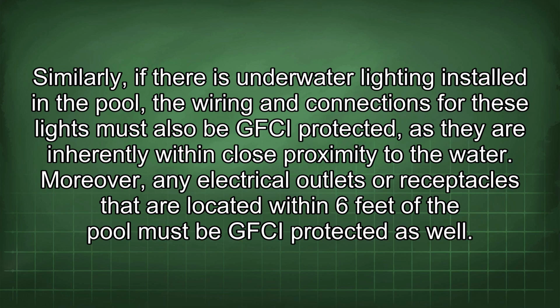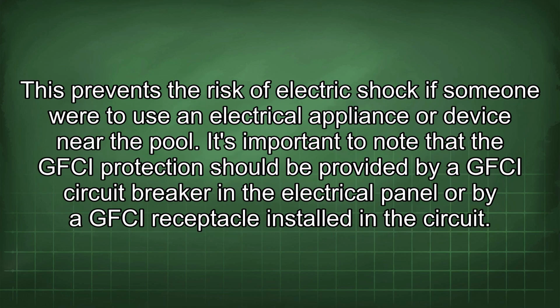Similarly, if there is underwater lighting installed in the pool, the wiring and connections for these lights must also be GFCI protected, as they are inherently within close proximity to the water. Moreover, any electrical outlets or receptacles that are located within 6 feet of the pool must be GFCI protected as well. This prevents the risk of electric shock if someone were to use an electrical appliance or device near the pool. It's important to note that the GFCI protection should be provided by a GFCI circuit breaker in the electrical panel or by a GFCI receptacle installed in the circuit.